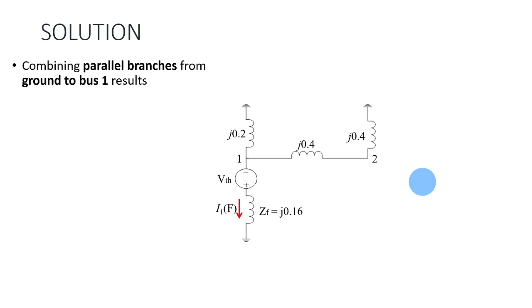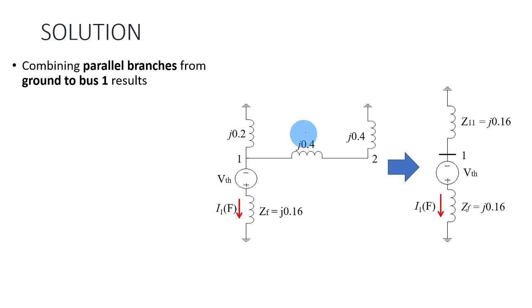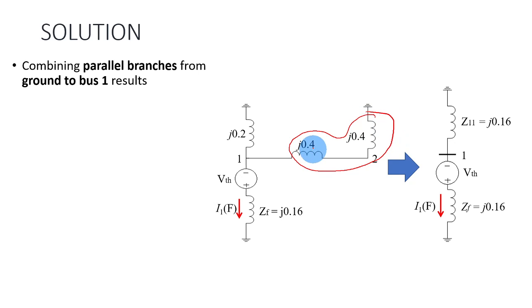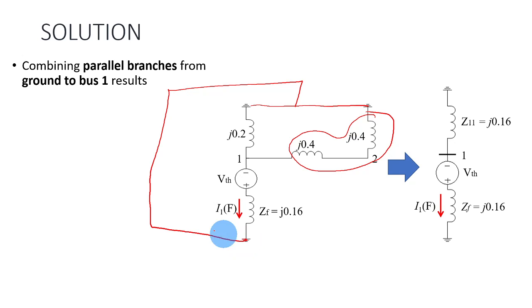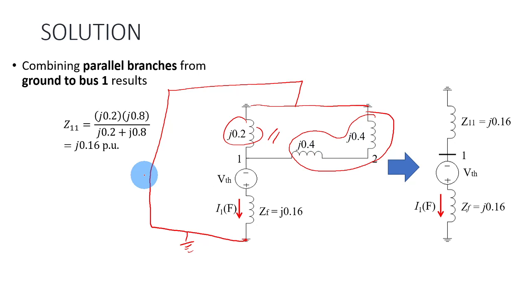You further simplify the network to find the Thevenin equivalent network. From here, you can see that you can combine all three together into one impedance. J0.4 here is now in series with this equivalent impedance, and these two together — because you can combine the common ground — J0.2 here is in parallel with these two together. If you parallel them, the equivalent impedance Z11, which is basically the Z-Thevenin, is j0.16 per unit. Z11 is the Z-Thevenin. The Z-Thevenin is 0.16.